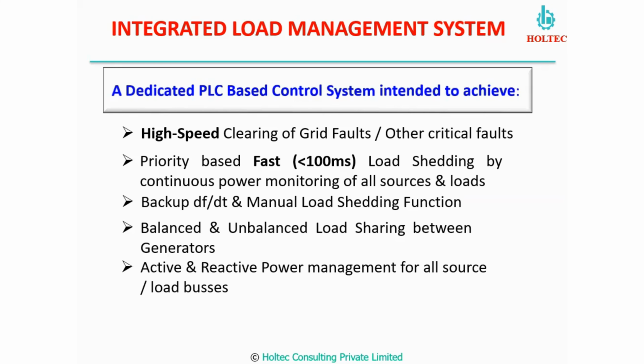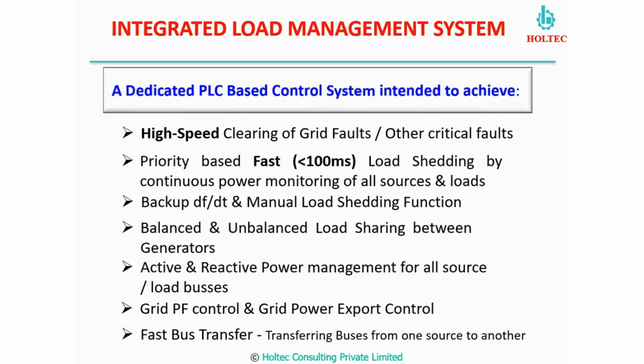And also we can manage active and reactive power on all sources and all buses, so that we can achieve the minimum losses in terms of distribution losses, or losses in the sources, generators, and the losses in the motors, if we are managing the active and reactive power. Then the grid power factor, I have already told, and grid power export, we can control. Then we can also have features like fast bus transfer.